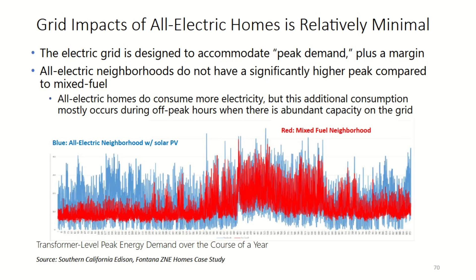This is a look at peak load on a transformer in 2 different neighborhoods - one mixed fuel, one comparable all-electric neighborhood with solar photovoltaic. Looking at this over 12 months, you can see a much more steady demand with the all-electric neighborhood, comparable or a little less than the summer peaks where air conditioning really drives demand. The peaks are very similar between mixed fuel and all-electric because air conditioning load is so dominant. So the infrastructure doesn't change a huge amount at the grid level.